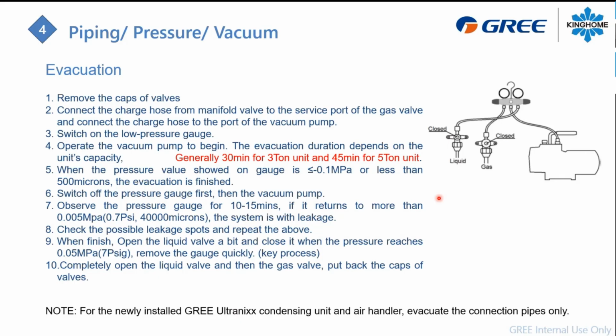When it's under 1,000 and stable, then your system is dry and there's no leak. So you can go and open your refrigerant line. You will have to open 4 service valves to make it work properly: 2 from the outdoor unit and 2 from the indoor unit.